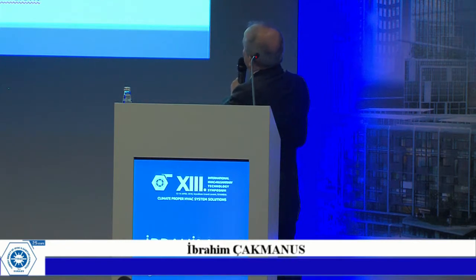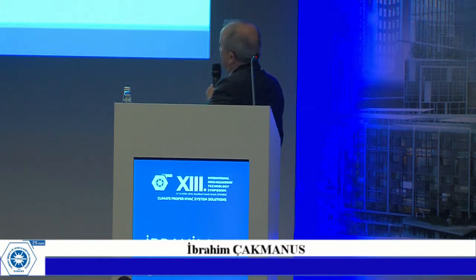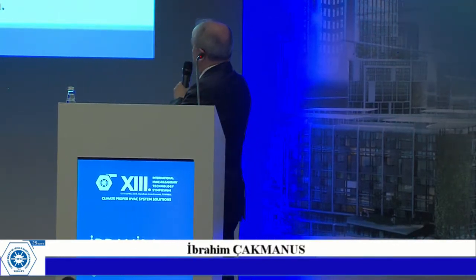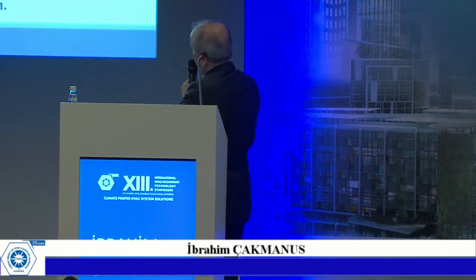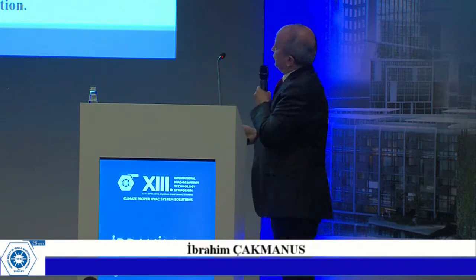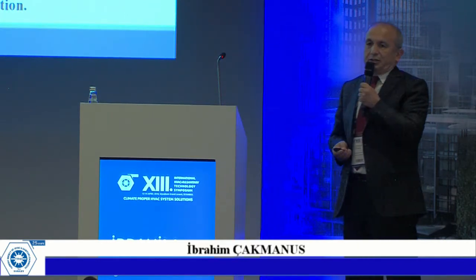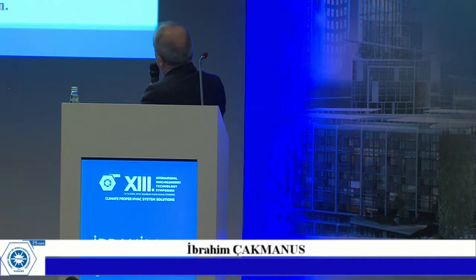Natural ventilation by opening the window was investigated first, and it was not found to be sufficient in volume, temperature, comfort, etc. Another alternative, fan-assisted natural ventilation, can meet the volumetric ventilation requirement. But what about temperature, overheating, or cold temperature in winter? This is not a comfortable alternative. Also, the overheating problem can't be met in this system.